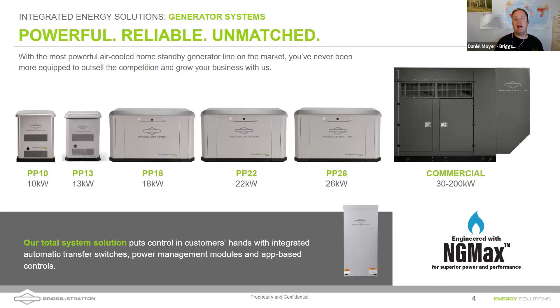Take a look at our generator lineup. I will say the only one that doesn't have the automatic 2-wire signal to start is that 10K. Every one of these other ones has the ability for 2-wire signal to start, so that a hybrid inverter, like a solar system, can automatically start it based on the state of charge of the batteries.